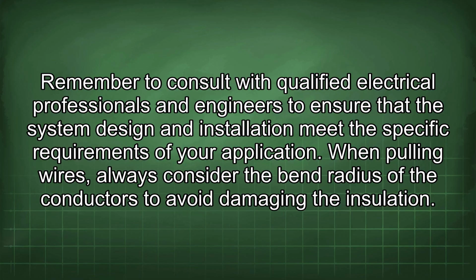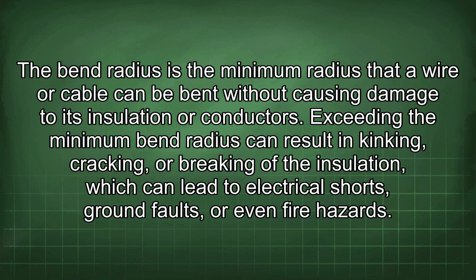When pulling wires, always consider the bend radius of the conductors to avoid damaging the insulation. The bend radius is the minimum radius that a wire or cable can be bent without causing damage to its insulation or conductors. Exceeding the minimum bend radius can result in kinking, cracking, or breaking of the insulation, which can lead to electrical shorts, ground faults, or even fire hazards.